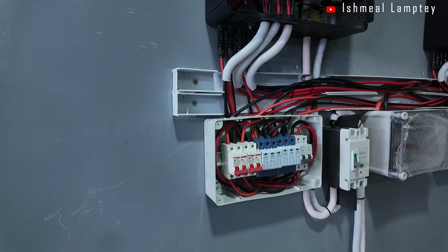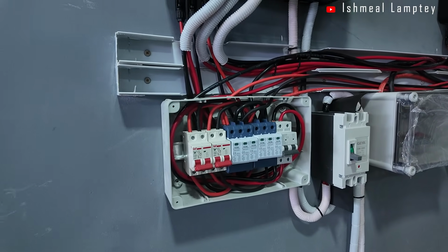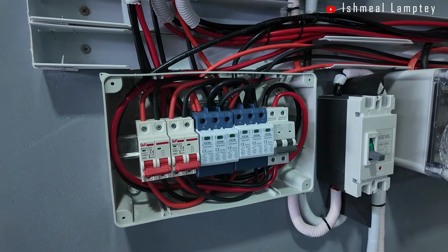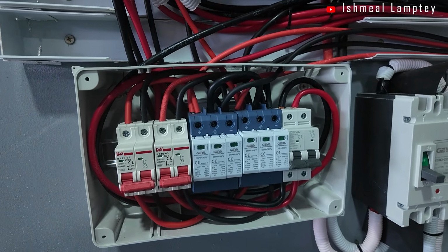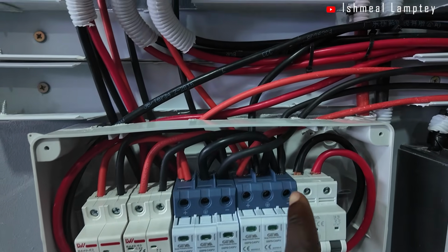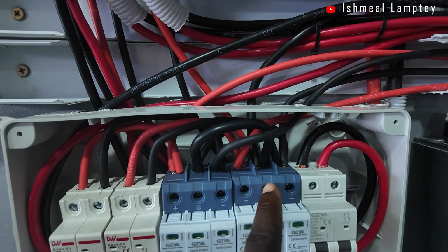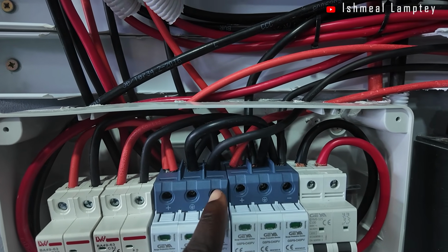So we routed our cable, mounted our inverters, and installed our breaker boxes. In each breaker box, we had an SPD for each array of panels. For the left breaker box, we had 2 SPDs for 2 arrays of panels.